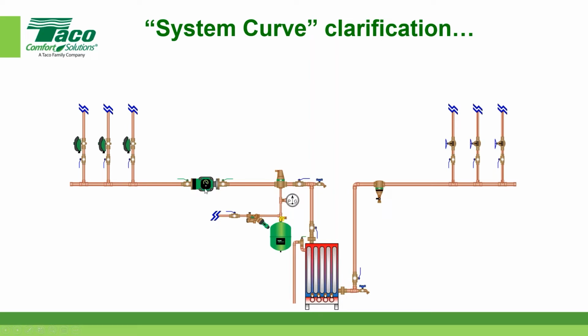And that circulator is going to know it as soon as it starts spinning. And within a few seconds, it comes up with a hydraulic resistance of that system. It's not the same thing as calling it a CV, the flow coefficient, but I suppose you could, if you knew at a certain flow what the 1 psi drop would be, you could give this a flow coefficient. But we generally don't talk about it that way within this realm. So the system curve is a shortened way of saying the particular resistance of the system you put the circulator on.